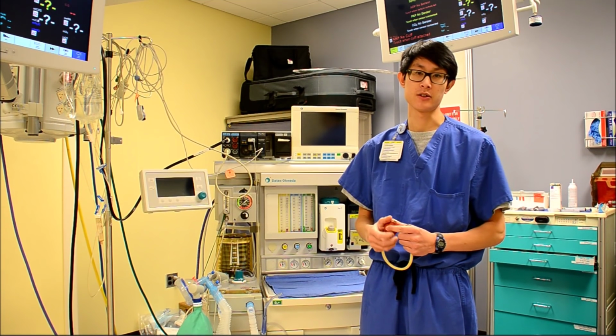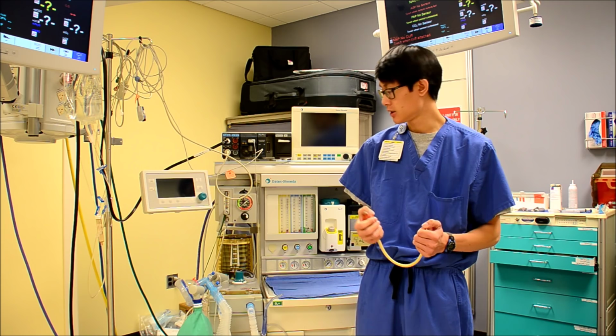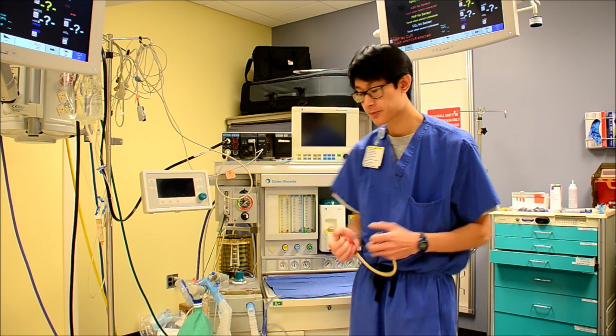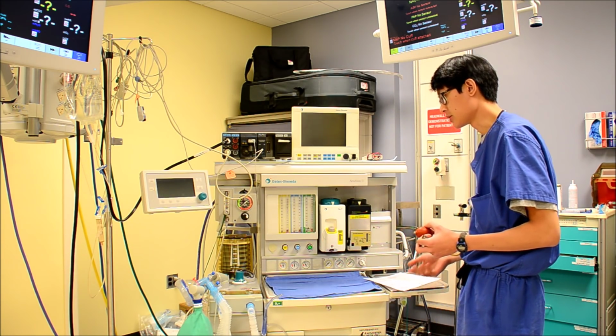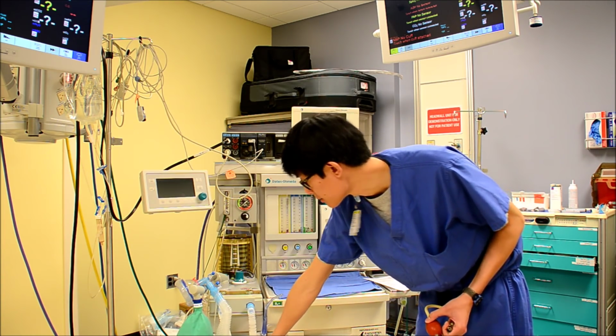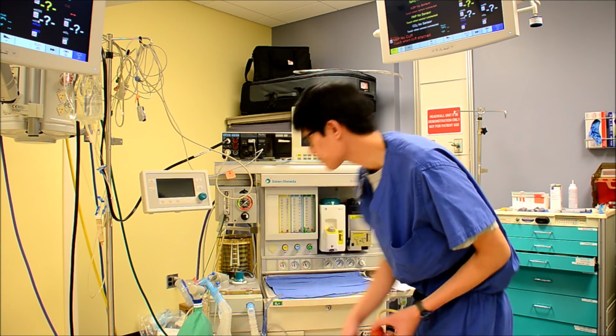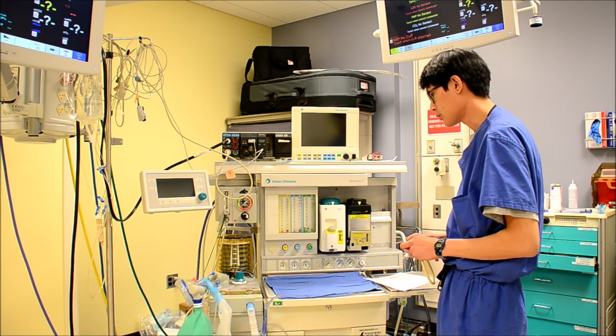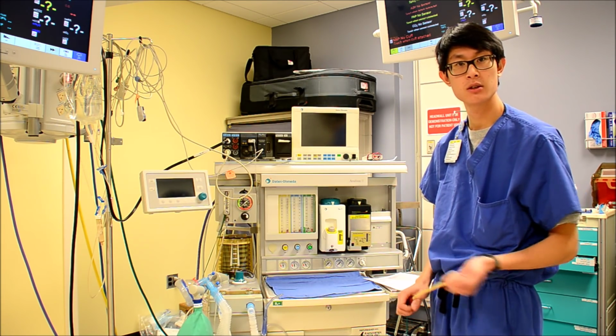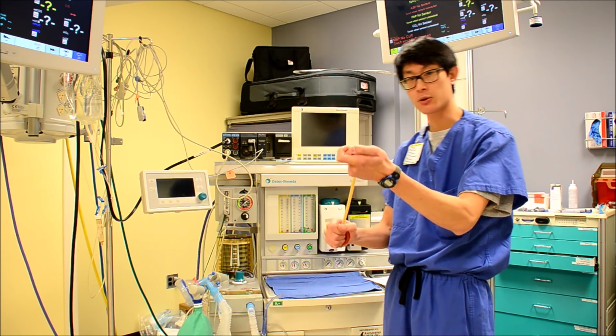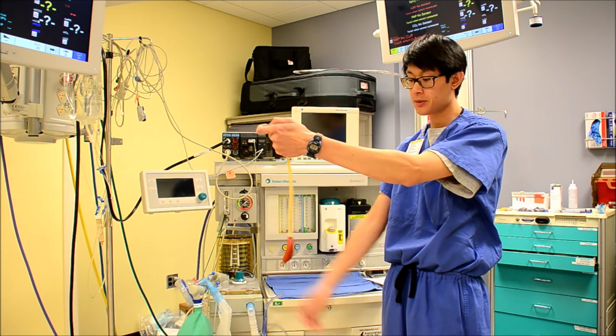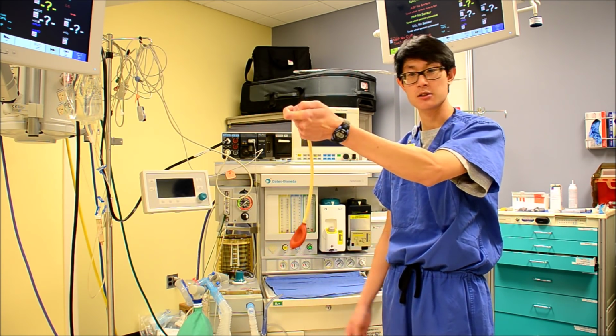So the next portion of the anesthesia gas machine checkoff is the low pressure system. This includes the vaporizers, CO2 absorber, and the common gas outlet. So the first thing, when you come in, just make sure your bulb is working. You'll go ahead and just cap off one end of it, go ahead and suction it. Make sure it stays for 10 seconds.